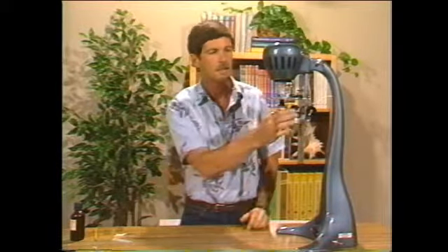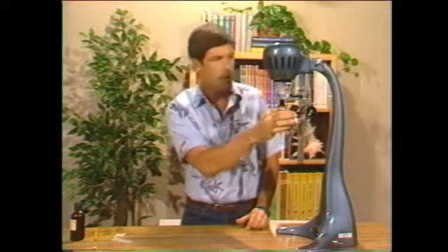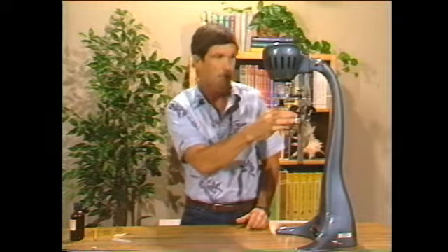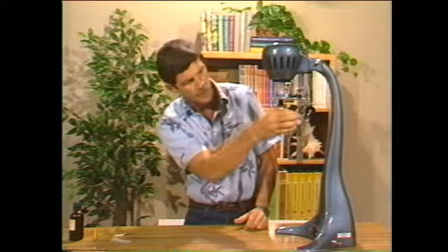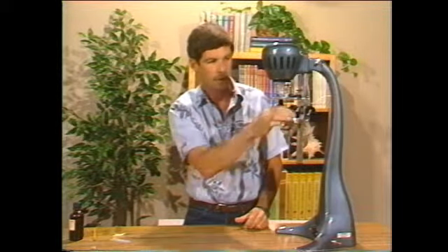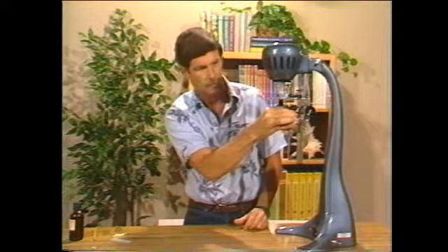First thing we'll take a look at are these 3 little turret objective lenses. Each one has a number on it. One says 6.5, one says 10, and one says 16. The lower the number, the more magnification. So if you want a lot of magnification, you set it till it clicks on the 6.5 lens. If you're in between any of these 2 lenses, you're not going to get any light to come through here. So you want to make sure it clicks into position. So I'll choose the 6.5 lens.